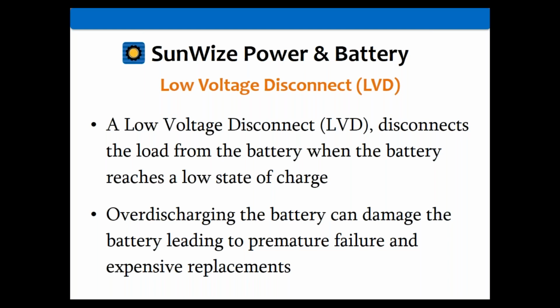Generally, they auto reconnect when the battery gets recharged up a little bit. It'll have a disconnect voltage and a reconnect voltage associated with it. Sometimes, depending on the unit, those are fixed. Sometimes they might be adjustable, on one or on both.